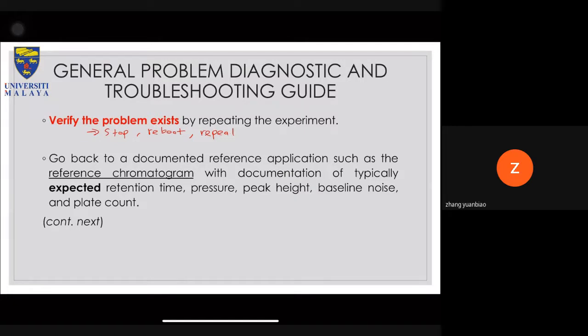Okay, so what you might want to do is go back to a documented reference application, such as, in this case, a reference chromatogram. In case that machine is solely being used by you, you might want to go back to your previous record and see whether the pressure is like this, whether the chromatogram is what was expected and whatnot. Or otherwise, if the machine is being shared with everybody else, normally you will have a book record. So you have record keeping on the users.